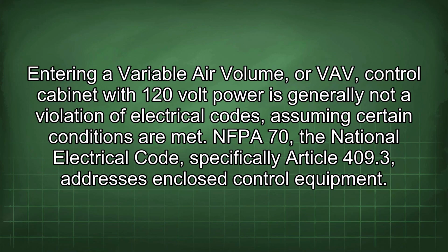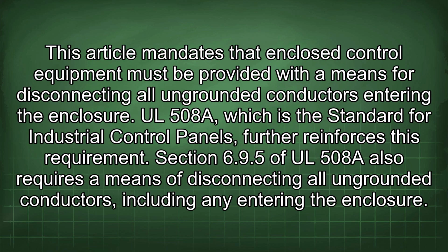Entering a variable air volume, or VAV, control cabinet with 120 volt power is generally not a violation of electrical codes, assuming certain conditions are met. NFPA 70, the National Electrical Code, specifically Article 409.3, addresses enclosed control equipment. This article mandates that enclosed control equipment must be provided with a means for disconnecting all ungrounded conductors entering the enclosure. UL 508A, which is the standard for industrial control panels, further reinforces this requirement.